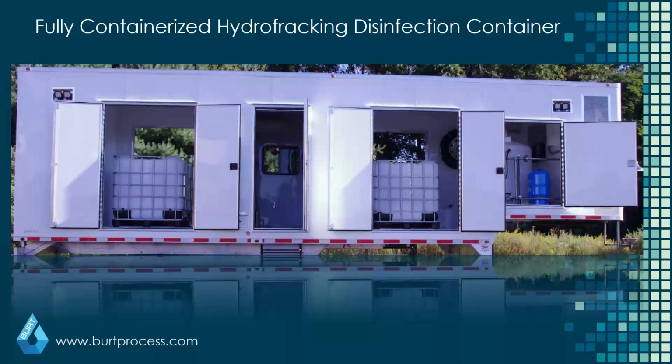When you're talking about a fixed base container design, it's really the same connections that you would need on a basic skid. You would need your power connection. Most of these are going to be some kind of 460 volt, although not exclusively the larger ones, because you do have to power the HVAC from the system as well, which will then have its own base transformers at that point. You have venting.